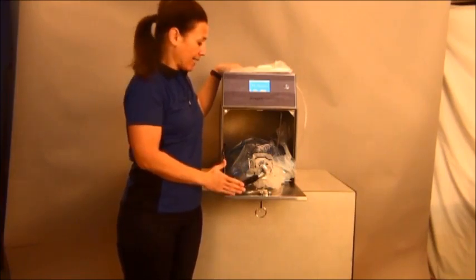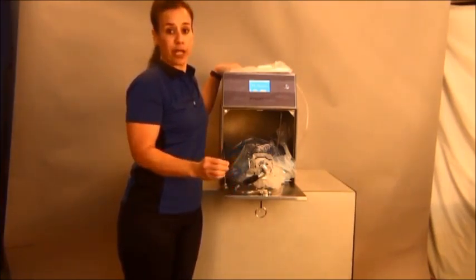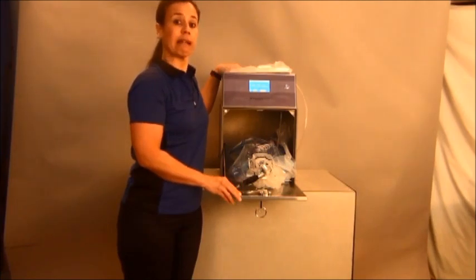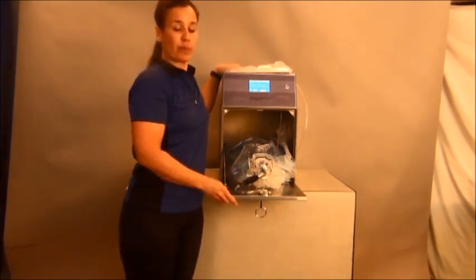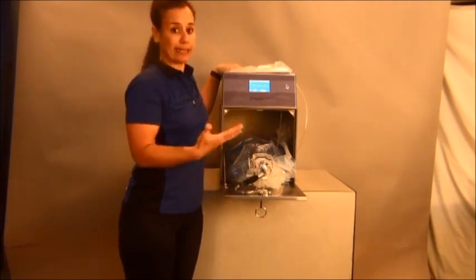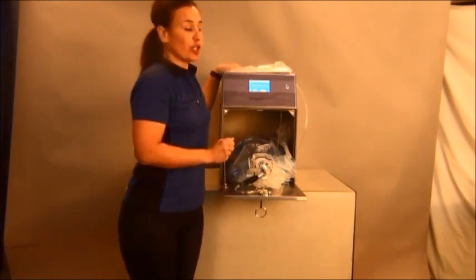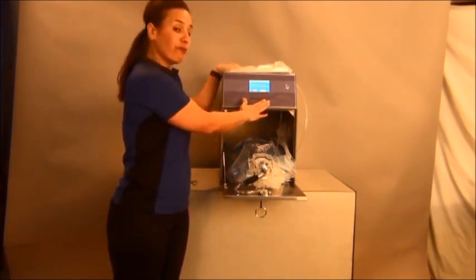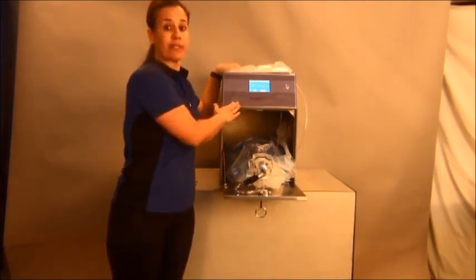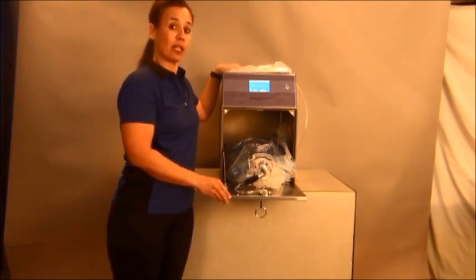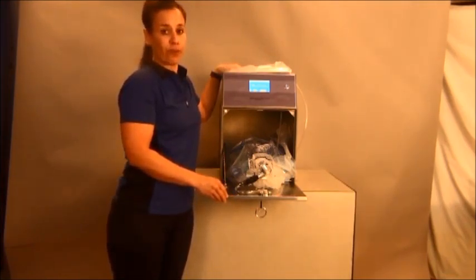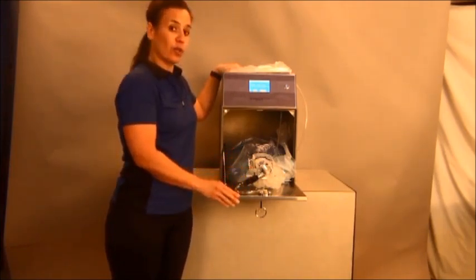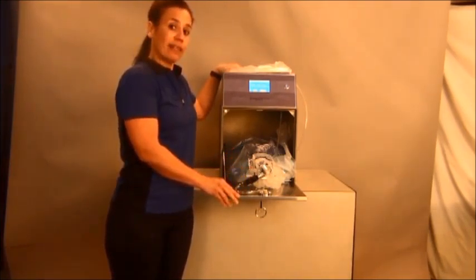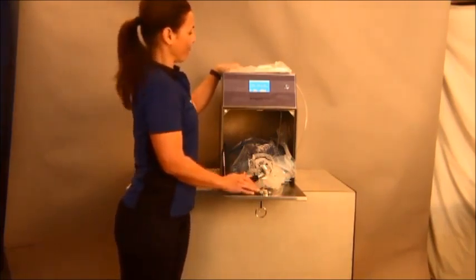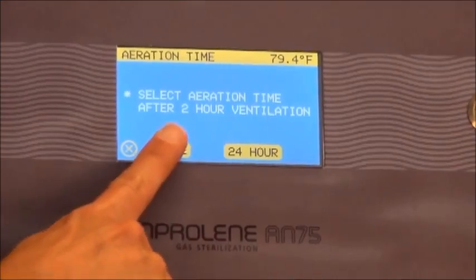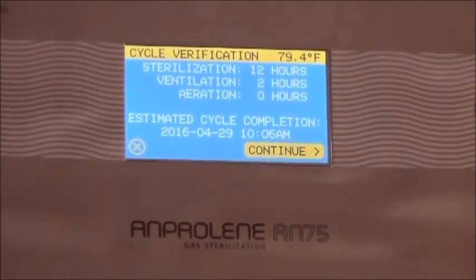Items that you're going to be sterilizing will absorb gas in some way, shape, or form, with the exception of metal and glass. The items that do absorb gas, we need to give the ability to release gas or aerate these items. You do have a choice for a 24-hour aeration cycle for items that the manufacturer has indicated need a longer aeration process, or items that you find are gas absorbent. For this cycle, we are running your standard system, so no extra aeration is needed. So we do not have to select extra aeration.